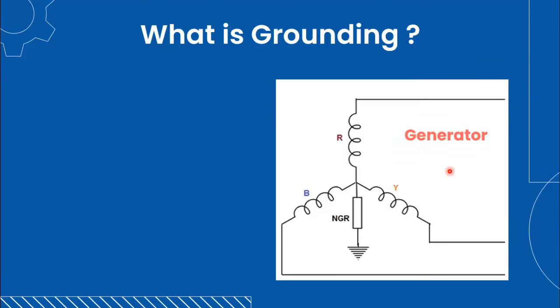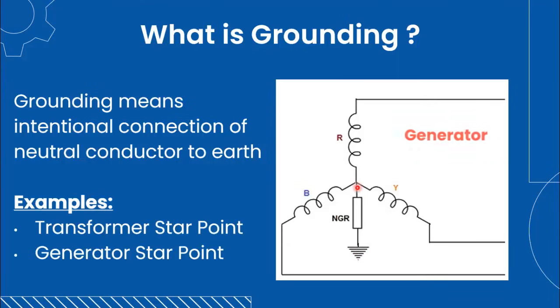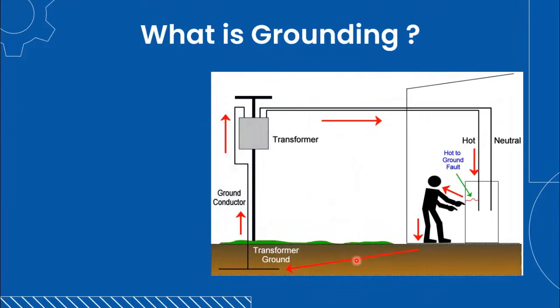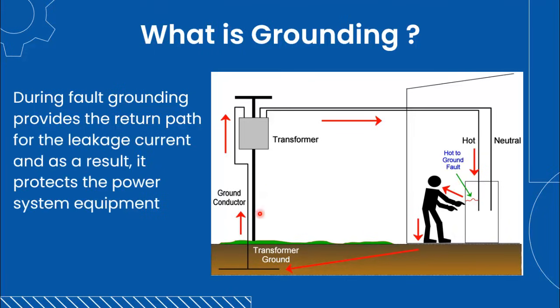On the other hand, grounding means the intentional connection of a neutral conductor to earth. Examples are transformer star point and generator star point. Here we can see that transformer neutral is connected with the earth. As the fault occurs, the current flows through the body into the ground, then from the ground to transformer neutral. This way the return path for leakage current is complete. As a result, a large current flows out of the transformer or generator which trips the circuit breaker and protects power system equipment.